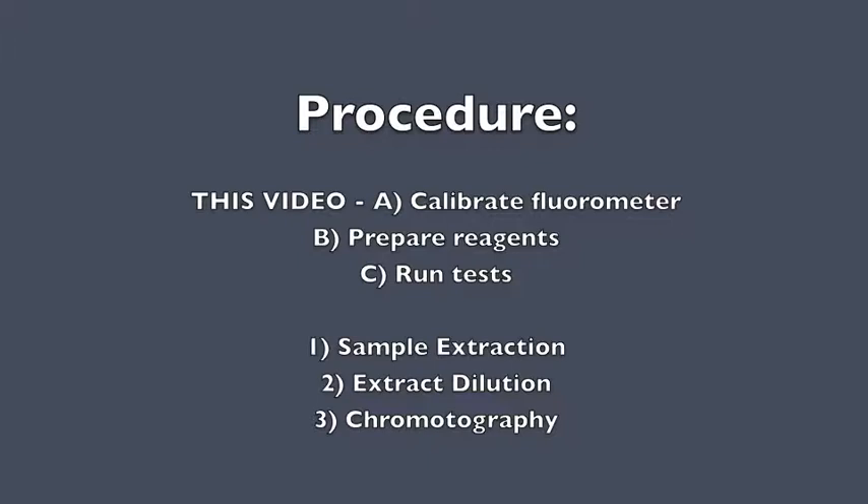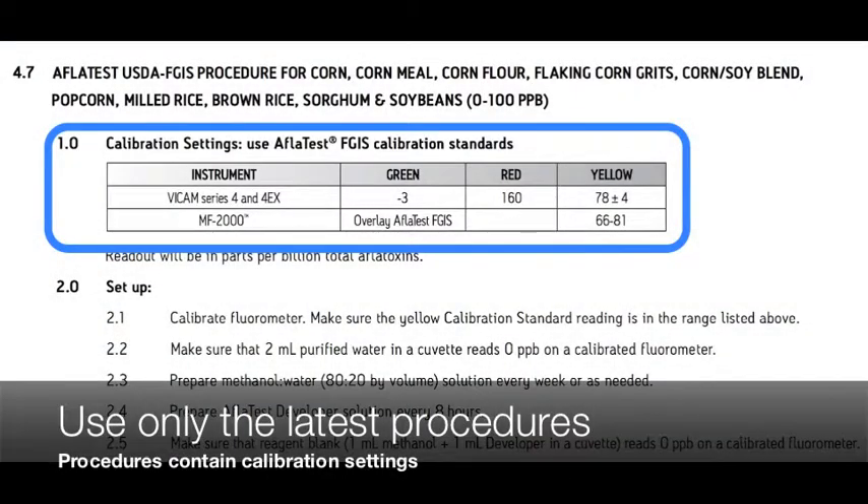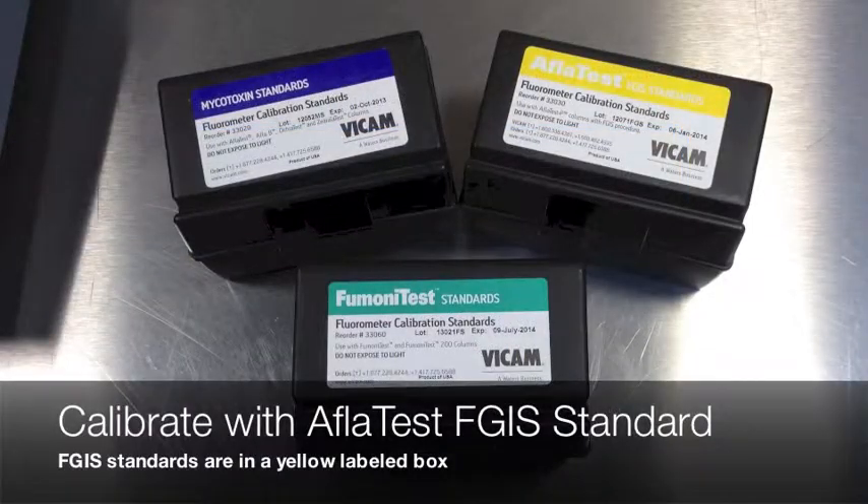Your fluorometer should be calibrated at least once per day. Calibration settings are subject to change. Use only the current procedures manual provided by Vicam. For the AflaTest FGIS procedure, use the yellow labeled standards box. Check the expiration date on your standards before proceeding.